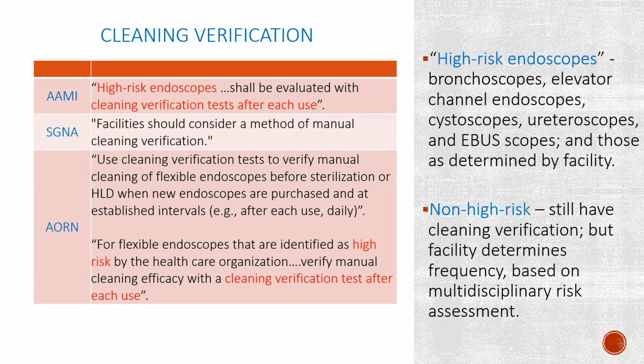AAMI and AORN declare the need for every cycle cleaning verification testing for high-risk endoscopes. The definition for high-risk endoscopes includes those associated with infectious outbreaks, those that are difficult to process. So it would include elevator channel endoscopes, so duodenoscopes and linear EUS scopes, as well as bronchoscopes, cystoscopes, ureteroscopes, and endobronchial ultrasound, or EBUS scopes. It can also include those as determined by facility, so a facility can choose to add to the definition of what they want to consider high-risk endoscopes. For non-high-risk endoscopes, for example, colonoscopes, gastroscopes, cleaning verification tests should be performed when new scopes are purchased and at established intervals, and this should be based on a multidisciplinary risk assessment.